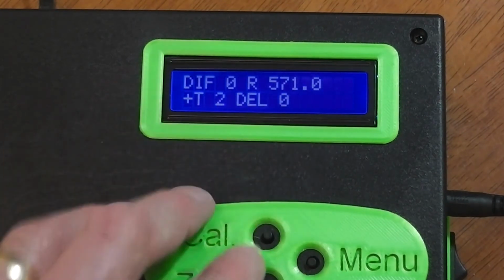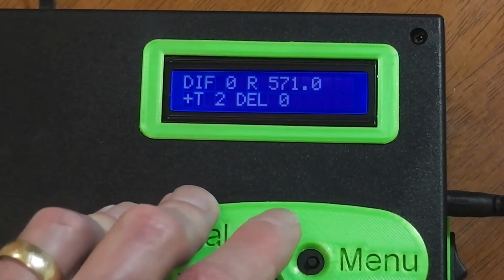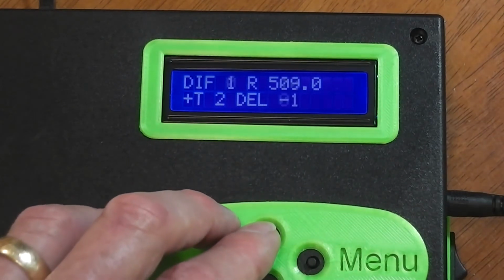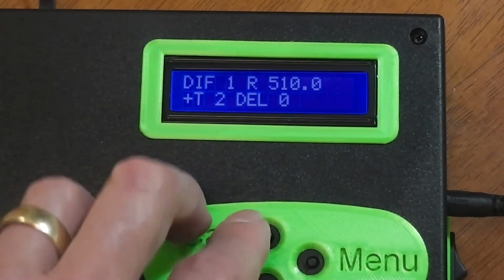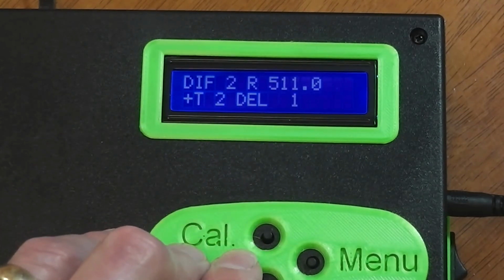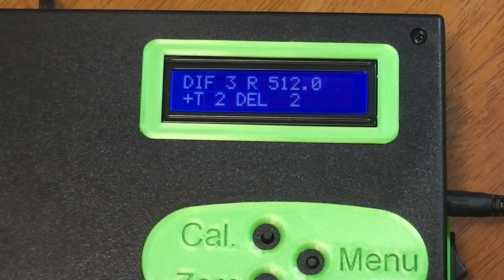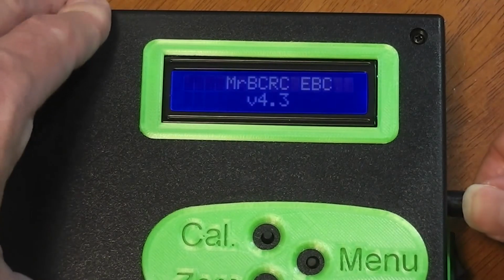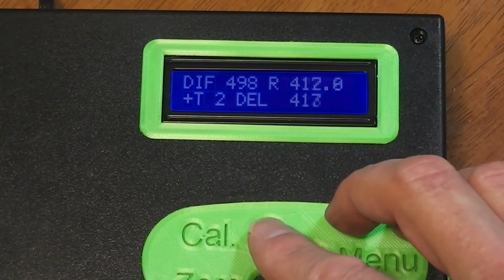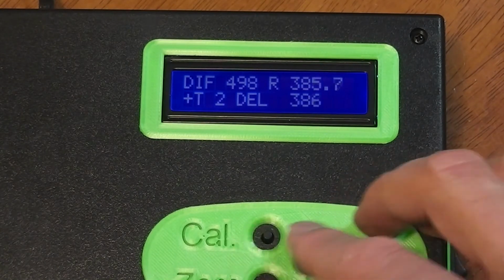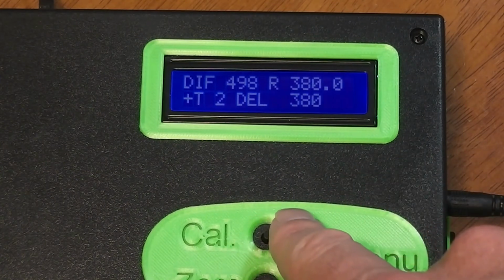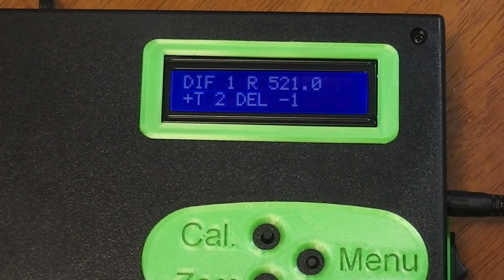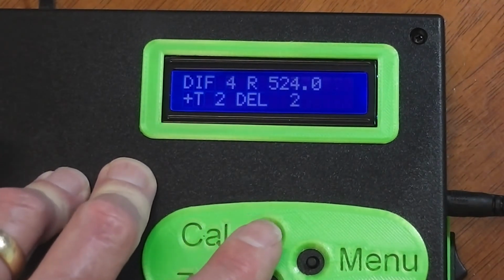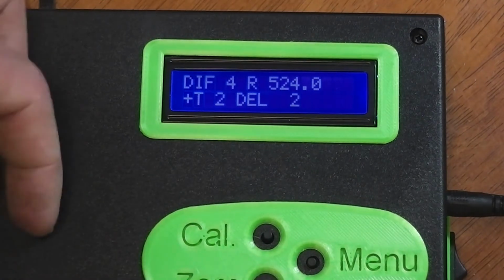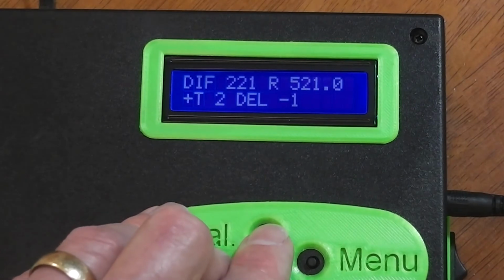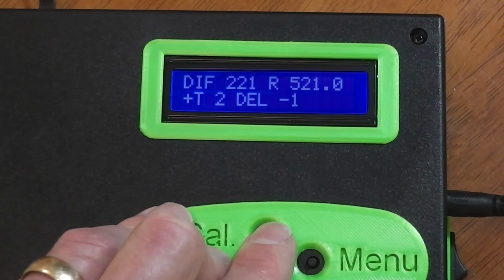So here we are back on here, and it's reset it because we come out of the menu, and I'm just going to do a re-zero or recalibrate. Now one of the things it will do, the calibration routine was different to the original first calibration, and that's because it detected that we weren't so far off where the zero was. So I'll just actually demonstrate that again. I think if I unplug it and power it back on, I know that reading's quite... Actually, yeah, I think we'll be right. So we do a calibration of this, it might do a full one. No, it's done a quick one. So yes, if it's quite far off, it will do a full calibration. If it's close, it'll just do a quick one. Because of course, as it's drifting by temperature, you don't want it to go into a full calibration mode when you really only need it to do a slight adjustment to center back on where the projectile is.